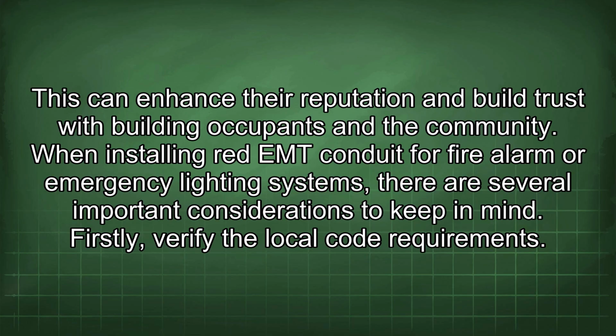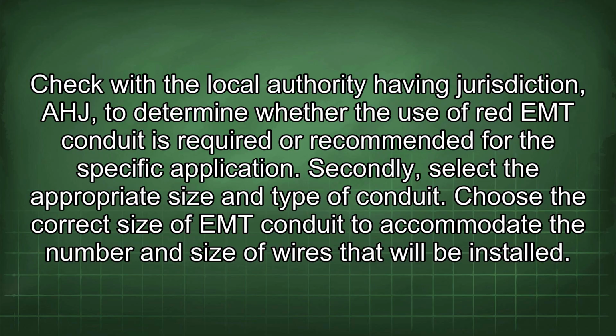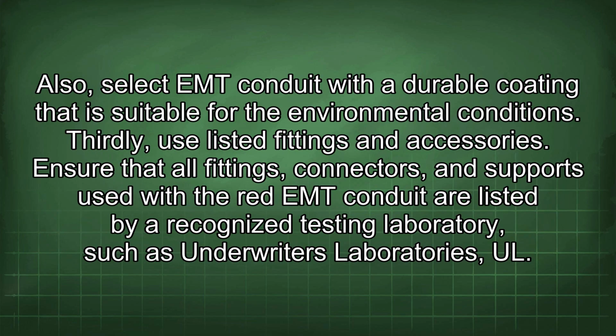When installing red EMT conduit for fire alarm or emergency lighting systems, there are several important considerations to keep in mind. Firstly, verify the local code requirements. Check with the local authority having jurisdiction to determine whether the use of red EMT conduit is required or recommended for the specific application. Secondly, select the appropriate size and type of conduit. Choose the correct size of EMT conduit to accommodate the number and size of wires that will be installed. Also, select EMT conduit with a durable coating that is suitable for the environmental conditions.